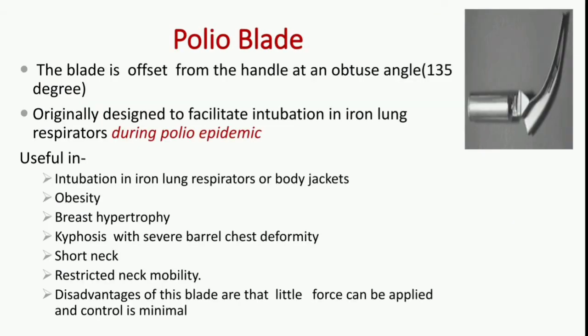Next is the polio blade. The blade is offset from the handle at an obtuse angle of 135 degrees. Originally designed to facilitate intubation in iron lung respirators during the polio epidemic, it is useful in iron lung respirators or body jackets, in obese patients, in cases of breast hypertrophy, kyphosis with severe barrel chest deformity, and persons with short neck and restricted neck mobility. The disadvantages are that little force can be applied and control is minimal.